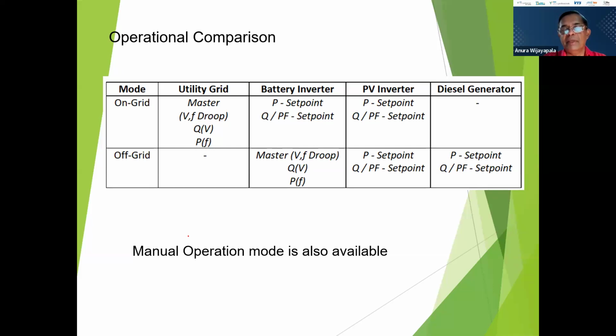In off-grid mode, we can have the diesel generator if desired, but in the worst case. Otherwise, PV inverters during the daytime, if solar generation is there, will generate depending upon resource availability. And then the battery will be the main performer during off-grid conditions, so we can program how the battery can be discharged and charged during the day, depending upon our requirement.